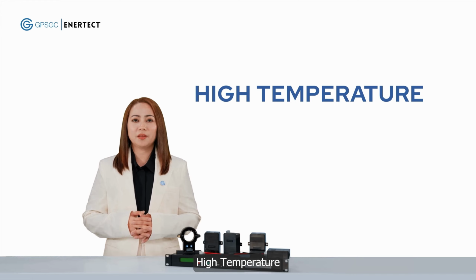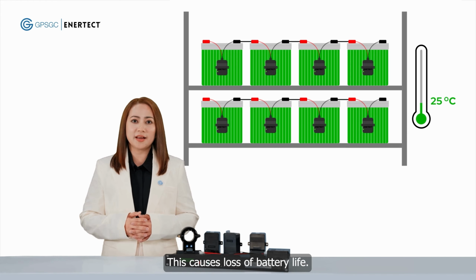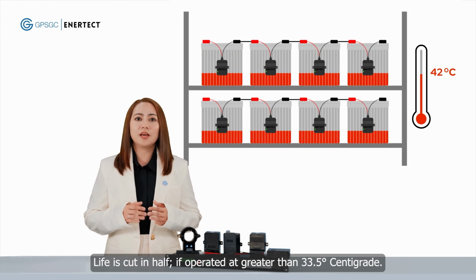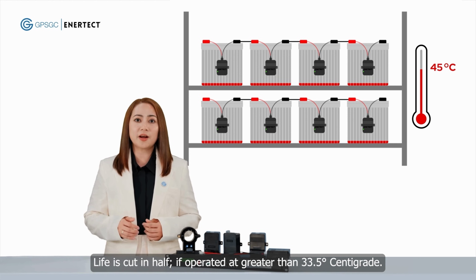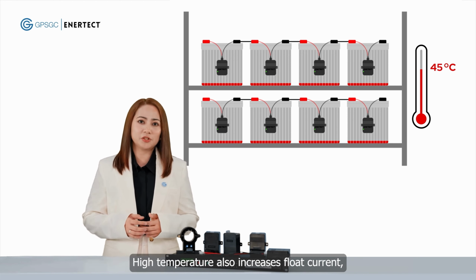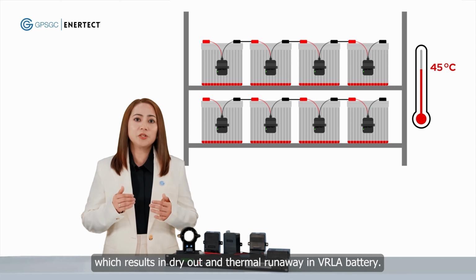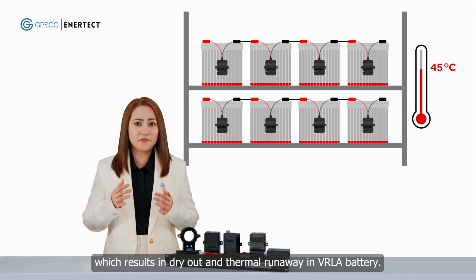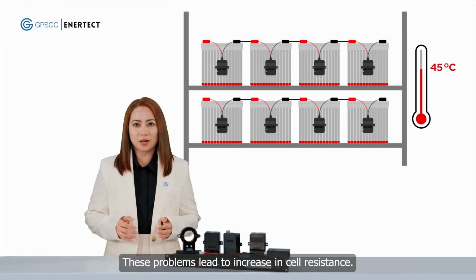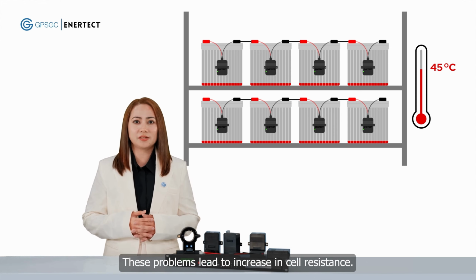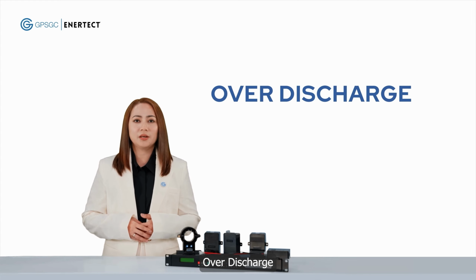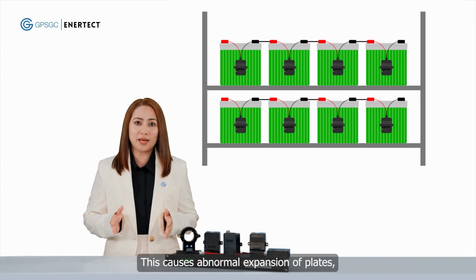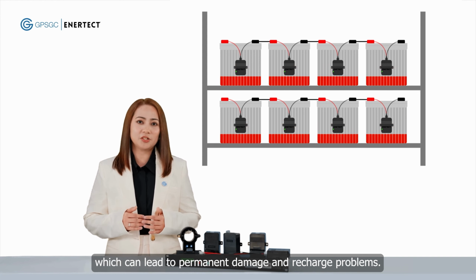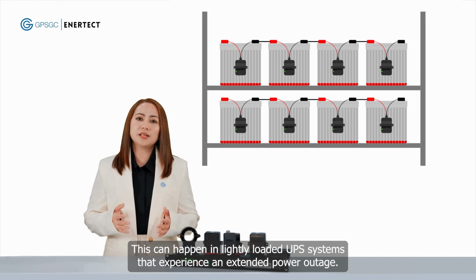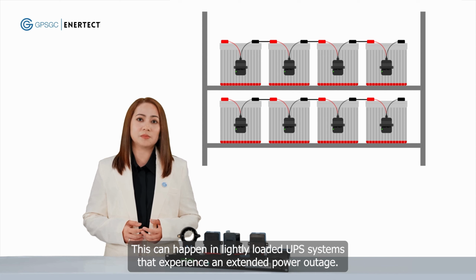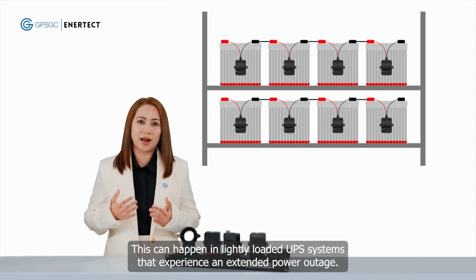High temperature. This causes loss of battery life. Life is cut in half if operated at greater than 33.5 degrees Celsius. High temperature also increases float current, which results in dry out and thermal runaway in VRLA battery. These problems lead to increase in cell resistance. Over discharge. This causes abnormal expansion of plates, which can lead to permanent damage and recharge problems. This can happen in lightly loaded UPS systems that experience an extended power outage.